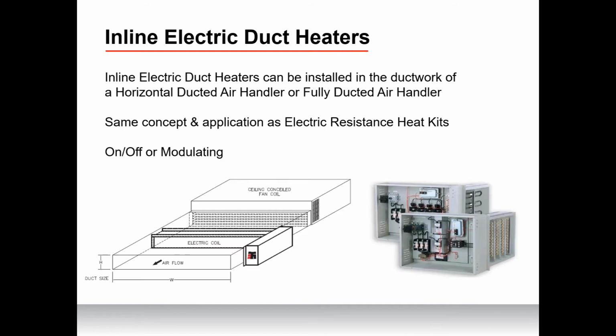You can also tie in third-party electric duct heaters to ducted indoor units. Here's an example of inline electric duct heaters. So think about these going on those horizontal ducted units. Here's actually a picture of one of these being integrated into a horizontal ducted unit. Inline electric duct heaters can be installed in the ductwork of a horizontal ducted air handler or a fully ducted air handler. They can work on the fully ducted systems as well too. Same concept and application as these electric resistance heat kits.